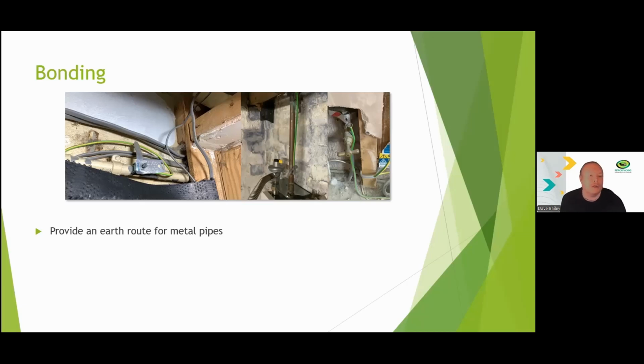It's an important safety feature to have. When a qualified electrician installs the system, they need to certify that it's safe, which requires this bonding. It's not a particularly big job, but it will add some cost to the project, so it's useful to capture this upfront so the electrician doesn't get a surprise and have to run a cable all the way around the house to this pipe. Good to evidence that so you can show them at the start.